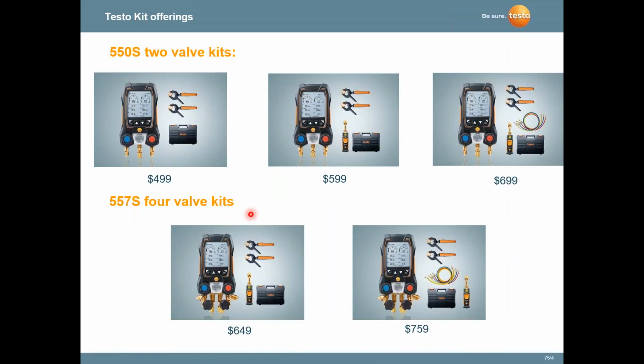People always ask me, what's the price on these digital gauges? They are what I consider affordable. We got a 2-valve and we got a 4-valve case. Ours comes in a hard carrying case. These are all calibrated, comes with a certificate of calibration, but a gauge, the 550S, has Bluetooth pipe clamp probes, hard carrying case. The list price is around $499. If you add the vacuum sensor to it, it jumps it up to $599. And if you add hoses, which have the low loss fittings, you're looking at $699.